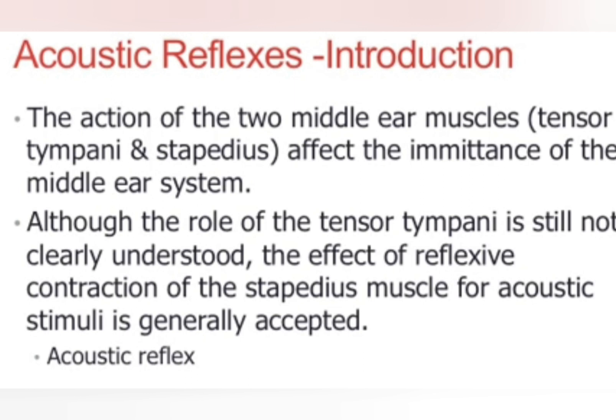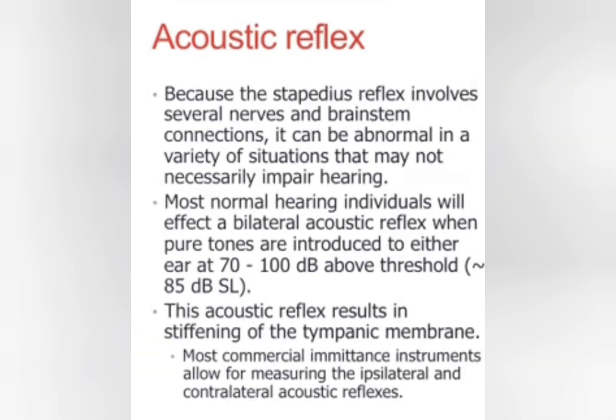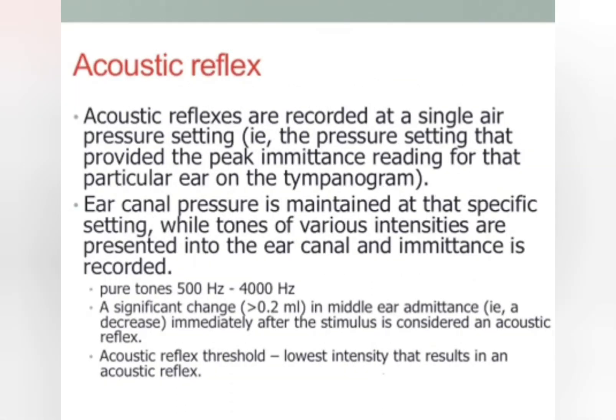The acoustic reflex involves the action of the tensor tympani and the stapedius muscles. When these muscles act, the compliance or stiffness of the tympanic membrane changes, and this change is recorded. It happens when you give a sound at around 85 dB above the hearing threshold level, which elicits the acoustic reflex, stiffening the tympanic membrane. A significant change in compliance is more than 0.2 ml, and this is picked up by the probe and recorded as the acoustic reflex.